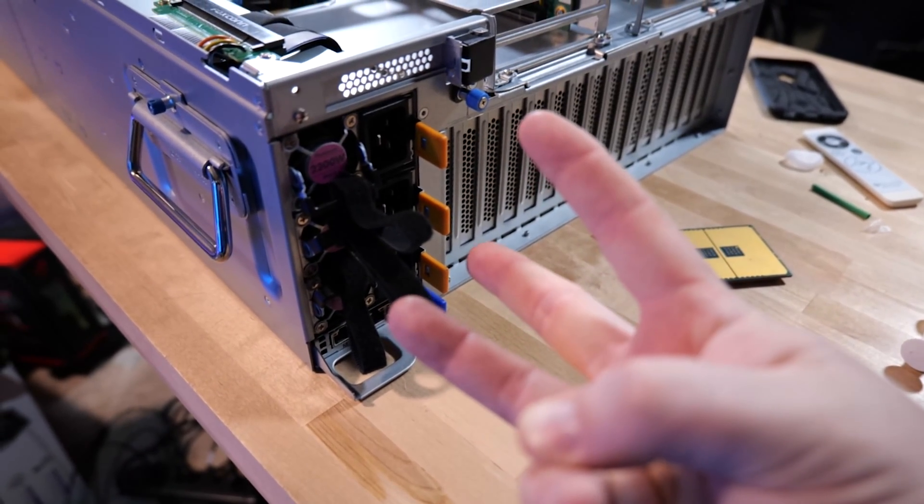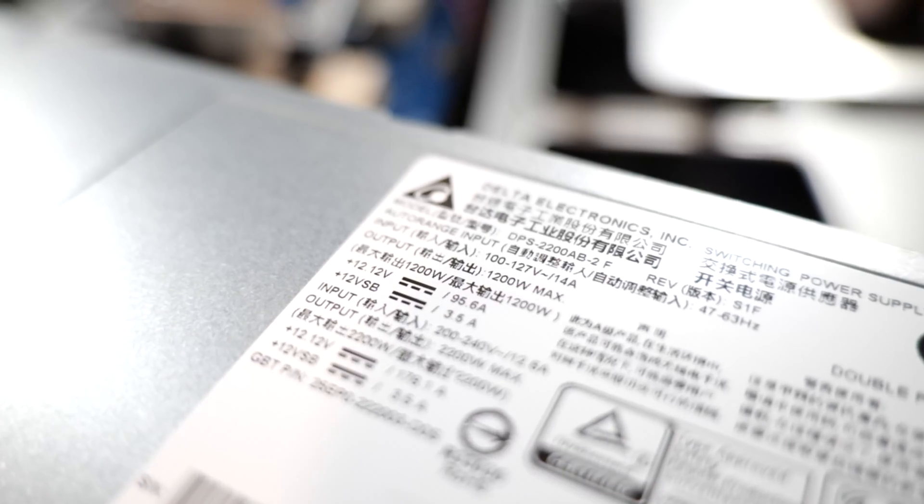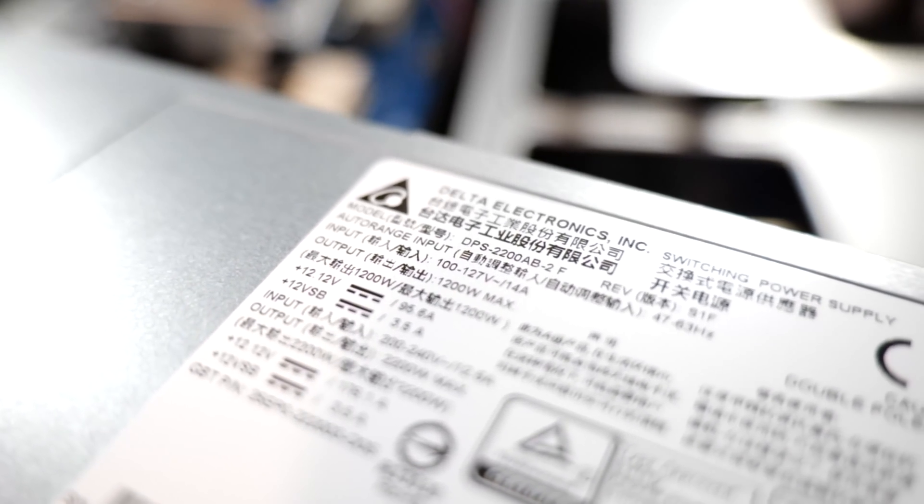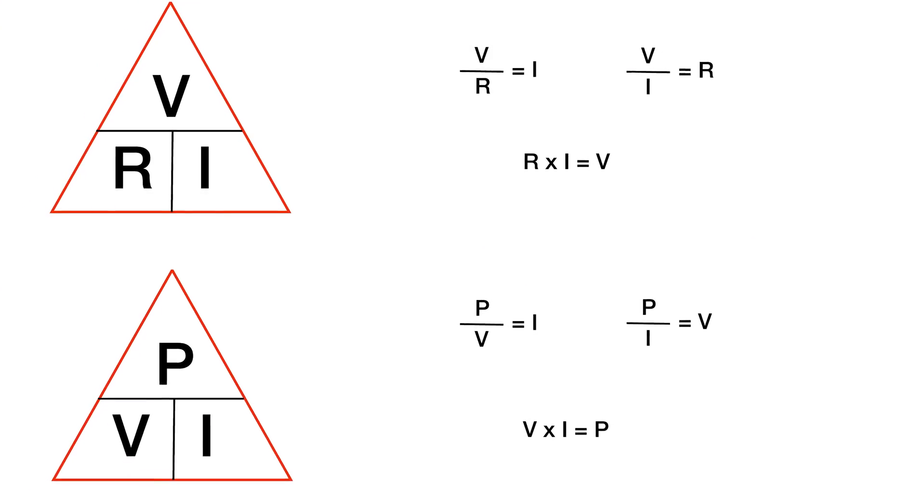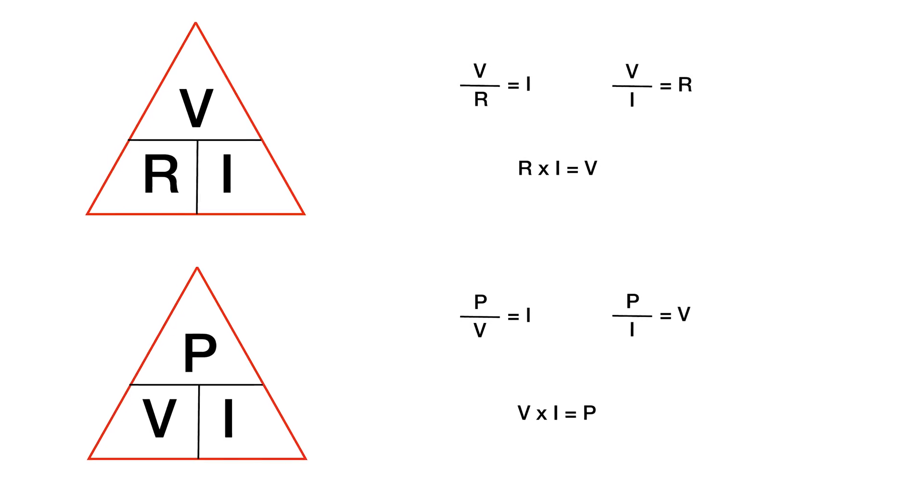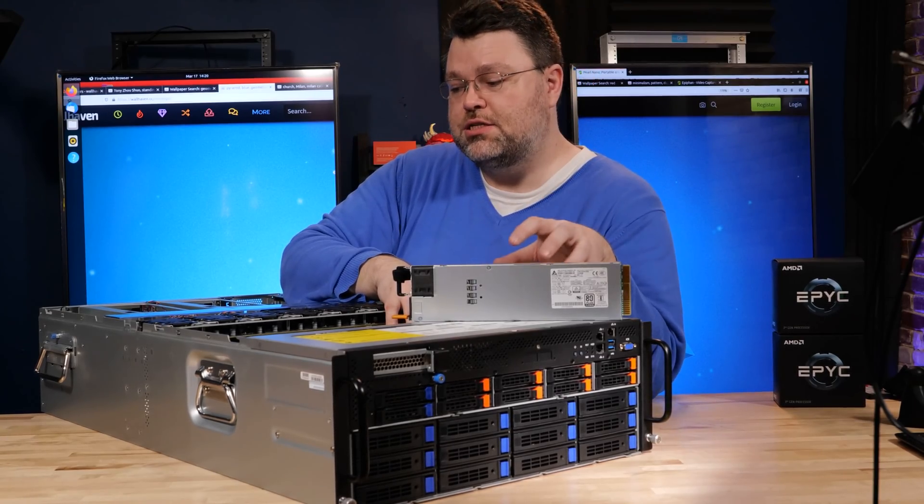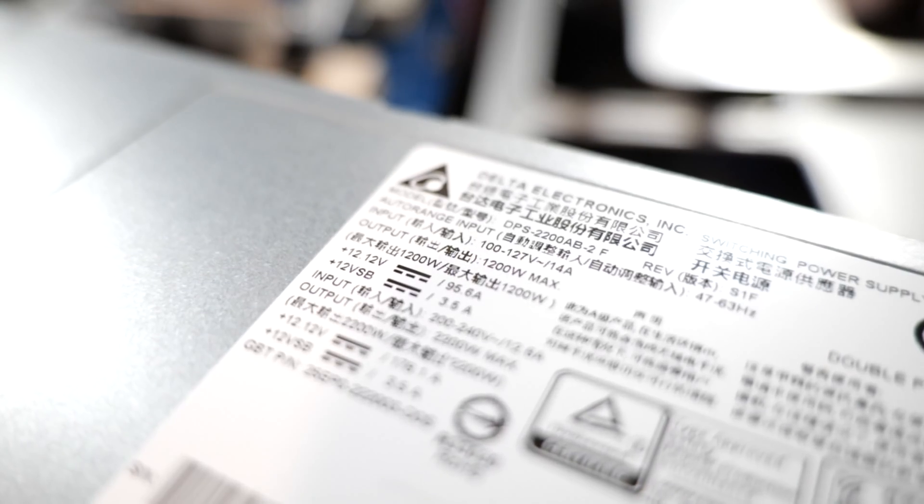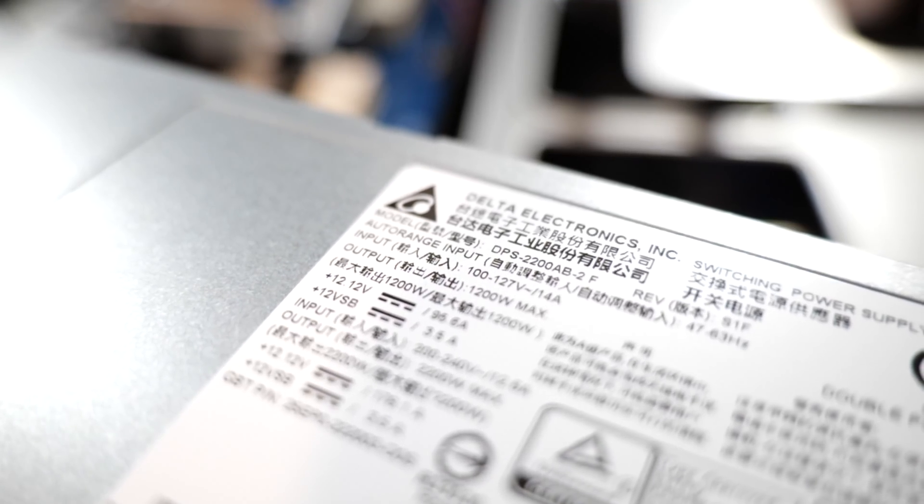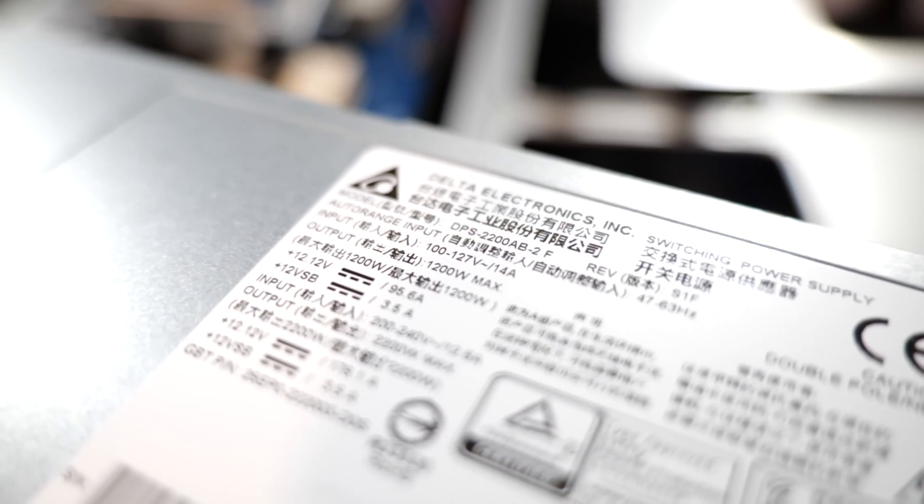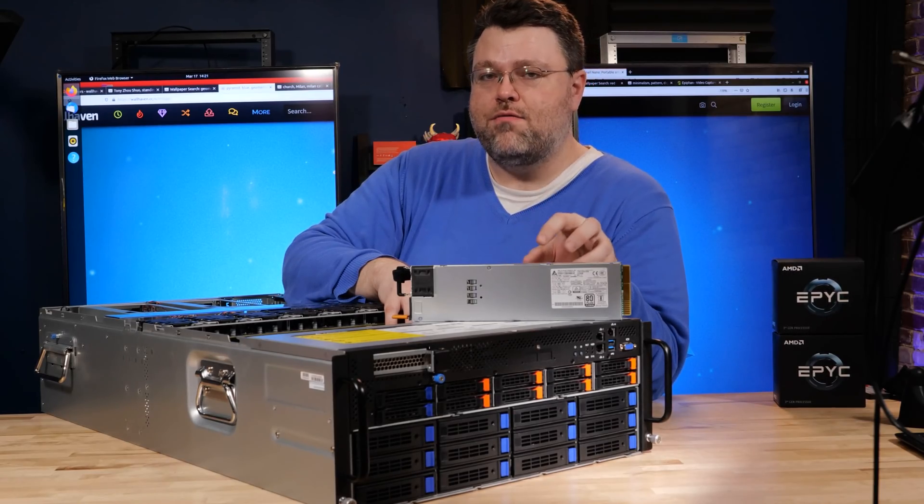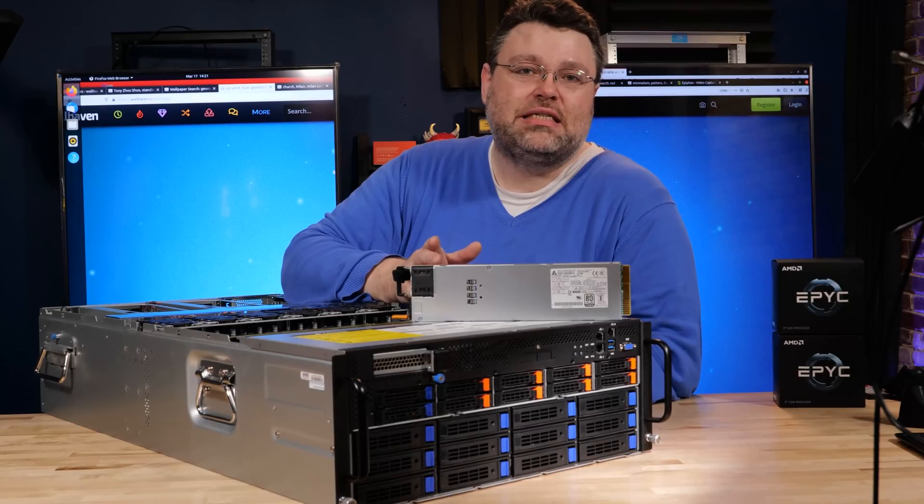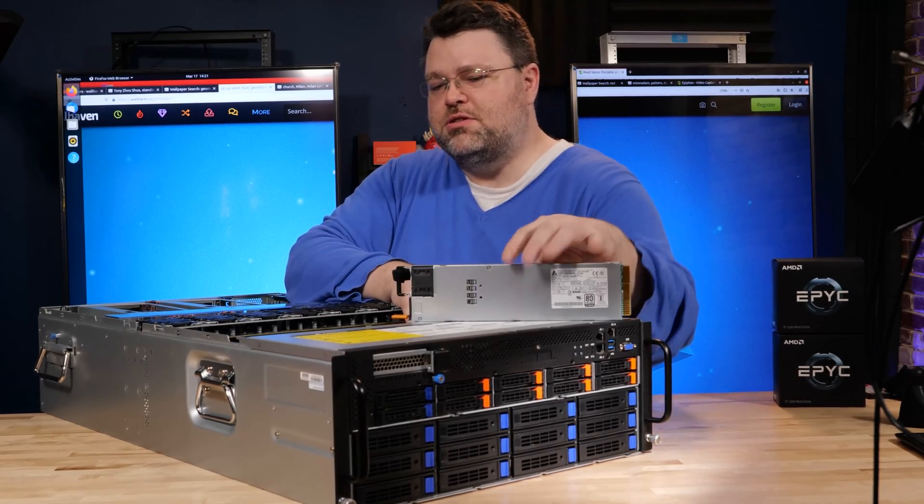Now here's a pro tip for you. These power supplies are dual mode. They're 120 volts or 220 volts or 240 volts, 230 volts. If you supply these chassis with 120 volts, you don't get as many watts. So if you're running chassis like these, not just a gigabyte chassis, but any server chassis, if you can give these kinds of high density chassis 220 volts instead of 110, assuming that your power supplies, you know, read the label, make sure it's supported, but you'll have more wattage headroom in order to do stuff. Hey Linus, if you made sure that your servers that have these kind of power supplies are getting 220 instead of 110, because all the watts. Just checking. Sometimes even seasoned admins will miss little details like that, so it's always worth the double checking.